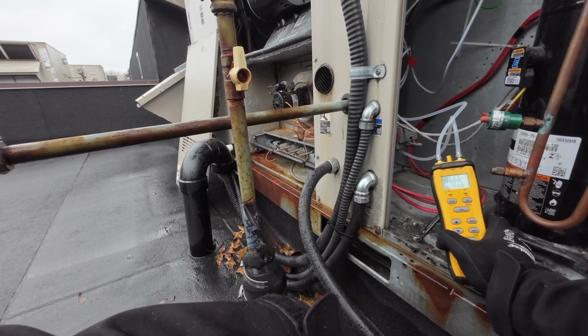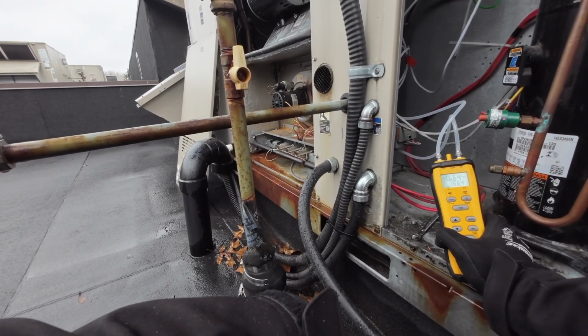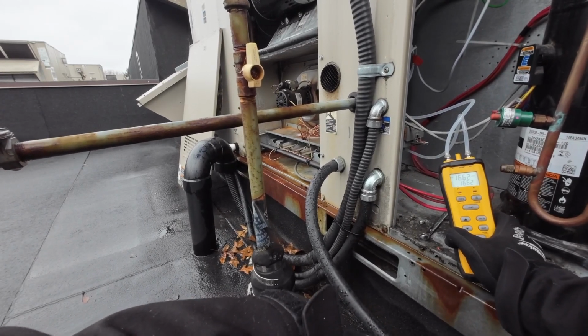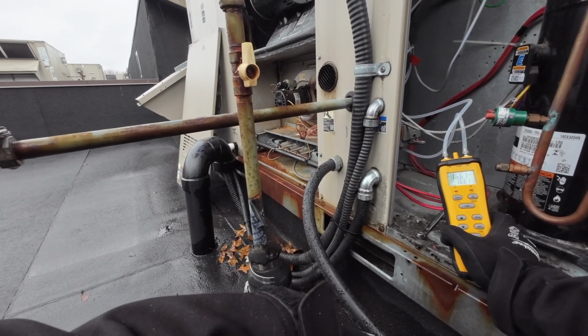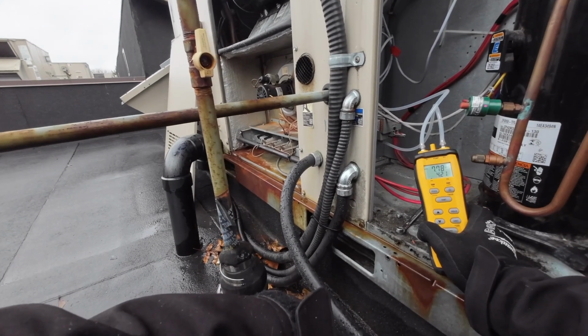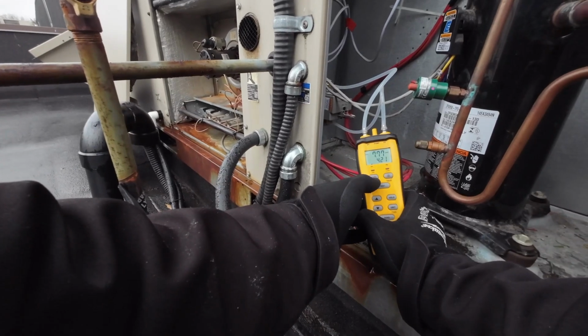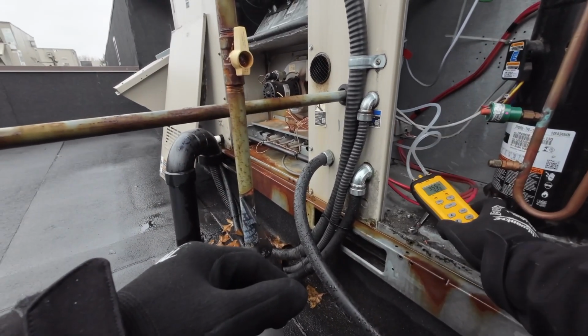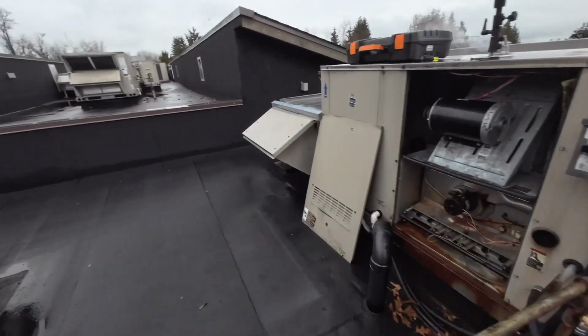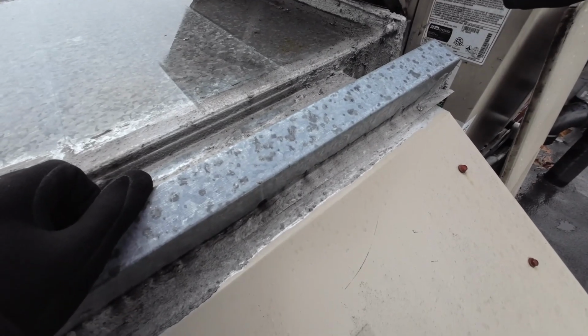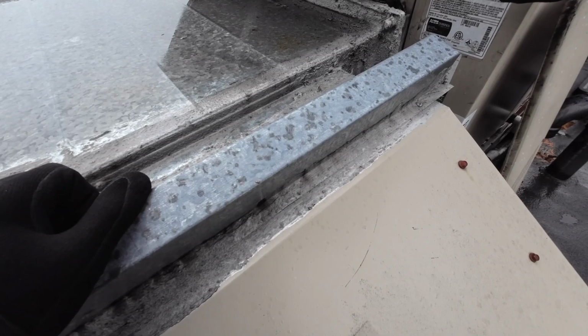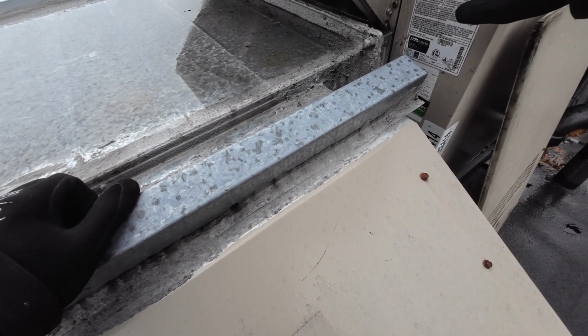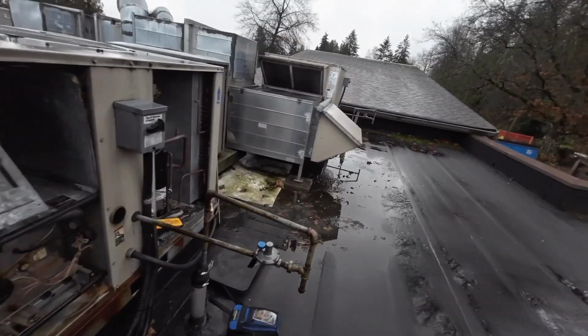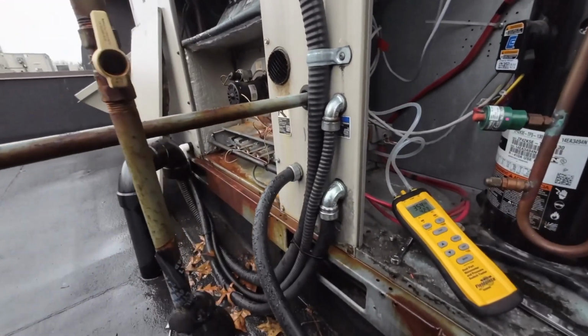Check our readings against the nameplate. Jumpers are on. Yeah, that's fluorescent. Alright, so we're 7.77 in, and we're at 3.56 out. It might move a little bit, but we'll give it a minute to settle down. What does the nameplate say? The nameplate on this thing says 3.5 manifold pressure. We want our max gas supply 10.5 to 14.5. So we're right in line there, and we're at 3.5. We're sitting at 3.53, 3.54. We're just splitting hairs.